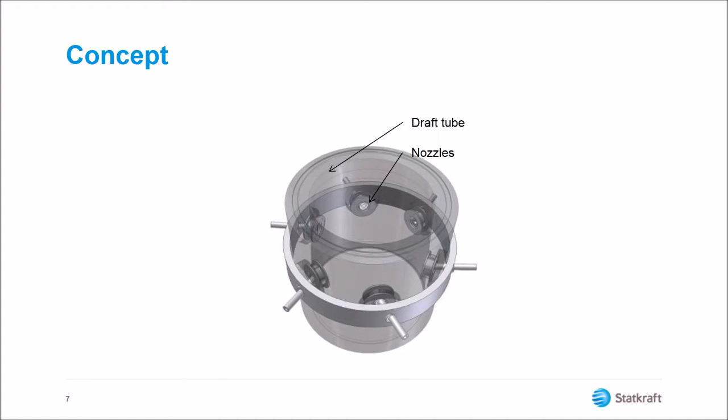The idea of the injection system is, as the name implies, to inject water in the opposite direction of the spin. This reduces the rotational energy and improves the flow through the draft tube. Ultimately, this should hinder the birth of heavy part load pressure pulsations.